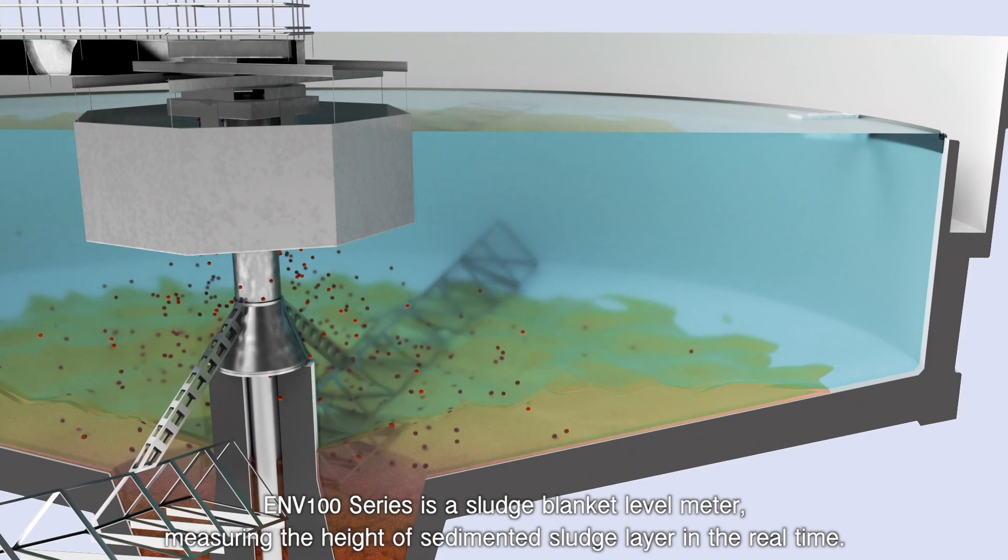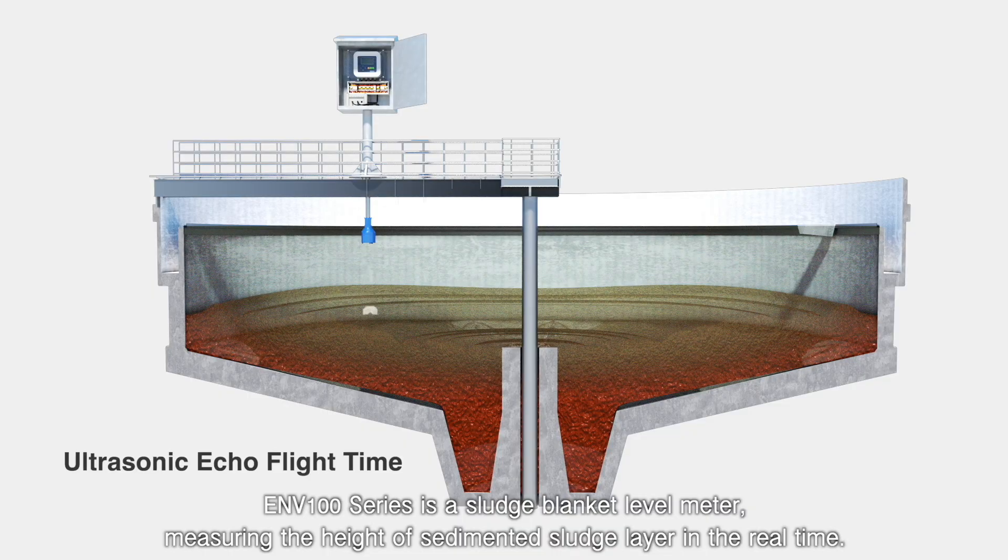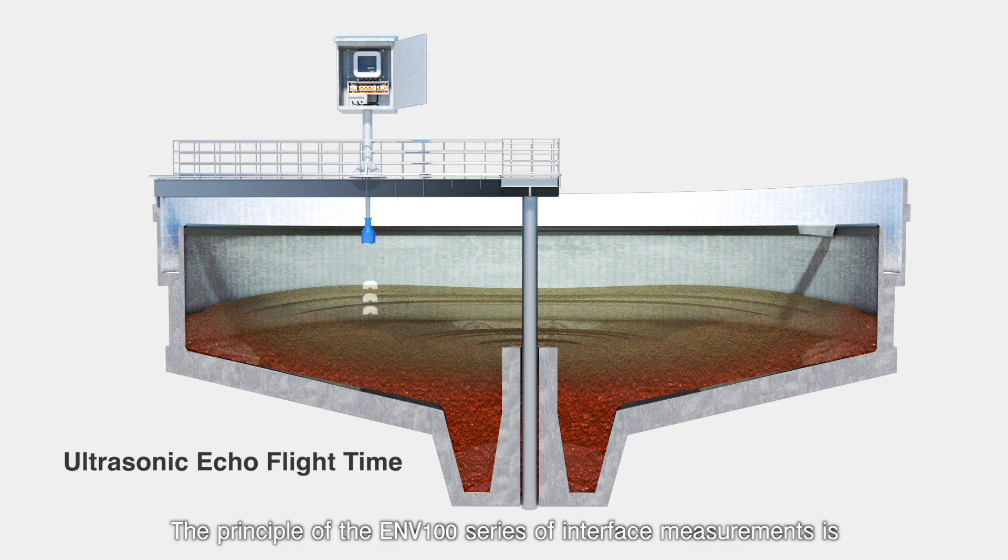ENV100 Series is a sludge blanket level meter, measuring the height of sedimented sludge layer in real time. The principle of the ENV100 Series of Interface Measurements is ultrasonic echo flight time.